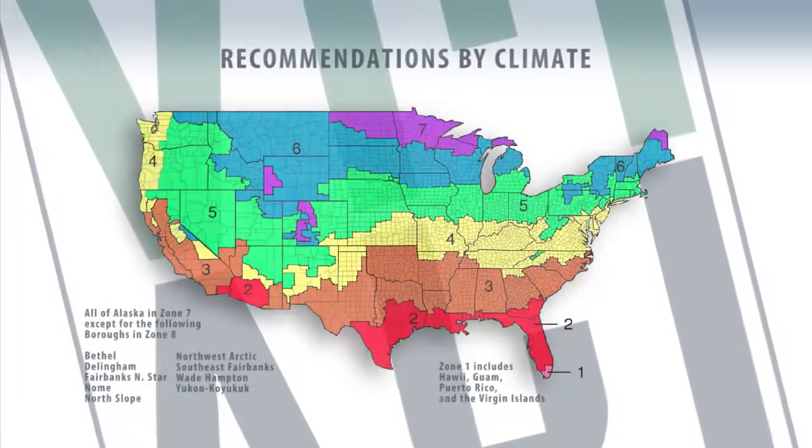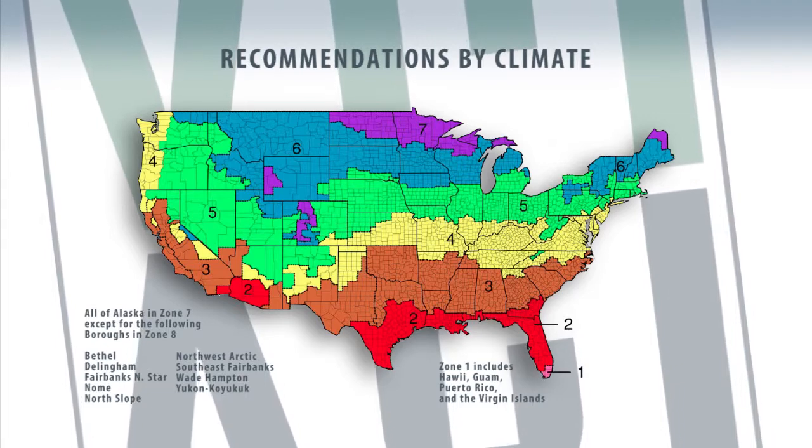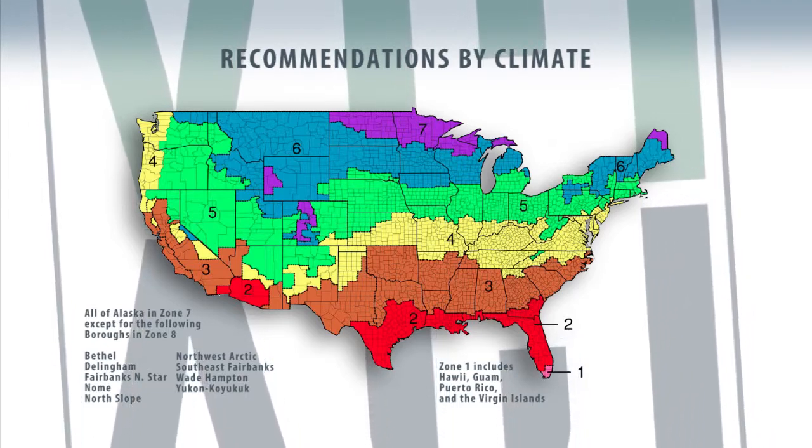Continuous insulation is referenced in ASHRAE 90.1, and actually the amounts of continuous insulation being referenced in ASHRAE 90.1 are on the increase. Typically, at least for the last several years, ASHRAE revises the 90.1 standard on a 3-year cycle. And they did it in 2004, 2007, 2010. And each cycle, you will see the requirements for above-grade walls, continuous insulation, increasing across all climate zones of the United States. This is not going to stop anytime soon.